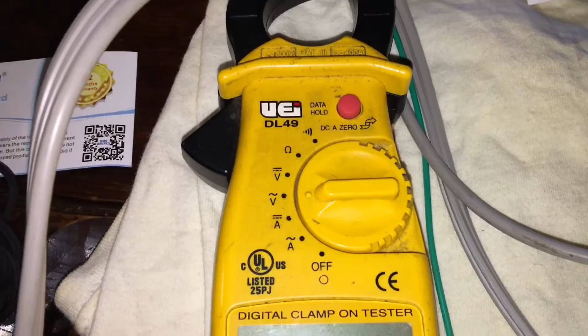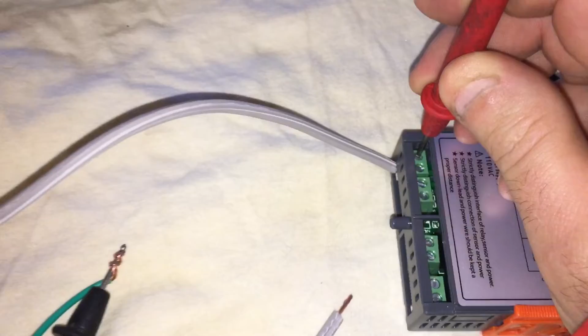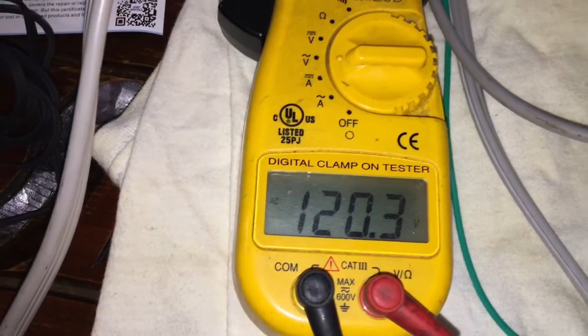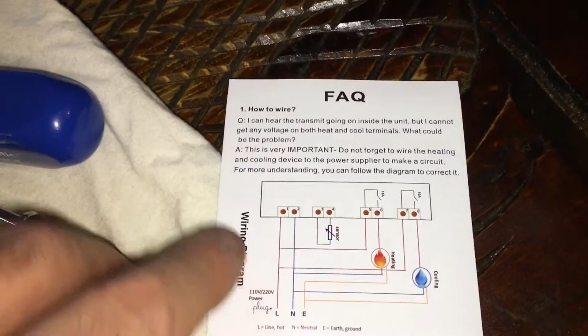So I'm going to go over here. I've got one of these wires, this one or this one, that's going to be the line wire or the hot wire, and one's going to be neutral, and the green is the ground. So I'm going to touch this to this wire because it goes right in there, and I have 120. So that tells me that is the line wire, and that is the one I do want for the line wire, for this wiring in this little INKBIRD controller.